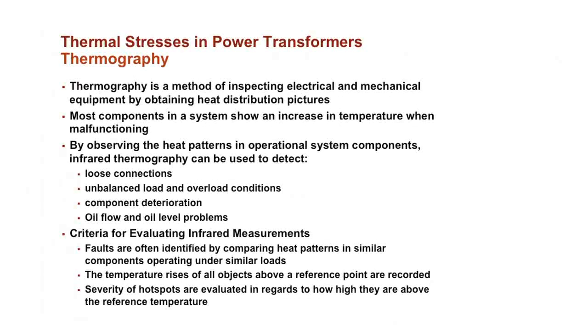Another very good tool is thermography. I think a lot of utilities use this now, where you take a thermal scan of a transformer, and you can usually see particular issues. One of the best things to see is if there's a hot connection on a bushing. Here is an example where there's a loose connection, or something's not right with the connection to the bushing. Now, this hot spot in itself is not a big deal, but what can happen is that heat can go into the bushing and then degrade the bushing over time. I personally know of lots of cases where that's happened, and it failed the bushing and then failed the transformer. So this is a good thing to be looking for regularly.